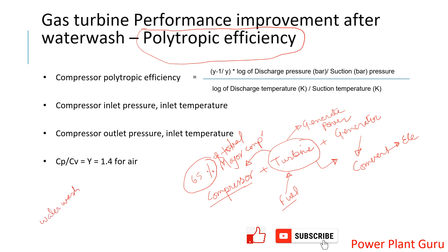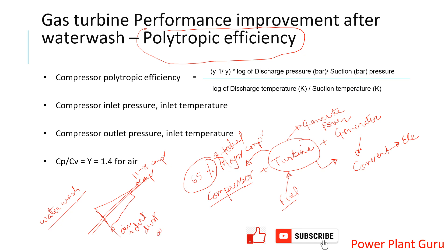There is another related concept — water wash. In a compressor, air enters at atmospheric pressure and compressed air exits. In a gas turbine, the compression ratio may be around 11 to 13. A large volume of air is pushed through the compressor blades, and this air brings dirt, dust, aerosols, etc. These keep depositing on the blades, changing the blade profile, which causes compressor efficiency to deteriorate day by day.